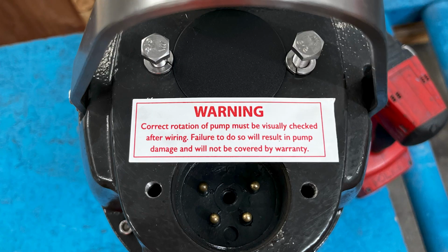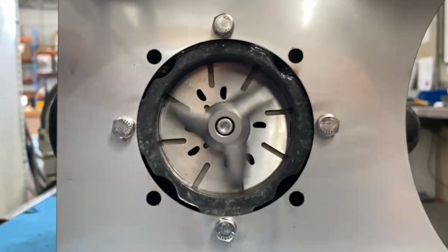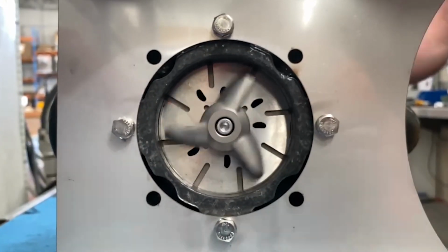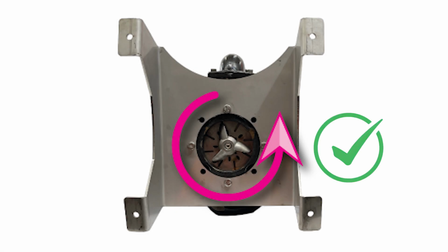Before moving on to the final testing cycle, specifically if you have a 3-phase pump, lift the pump out of the well and check your pump has the correct rotation upon powering up. This check is a visual check that should be validated against the markings on the pump. This check is not necessary for single-phase pumps.